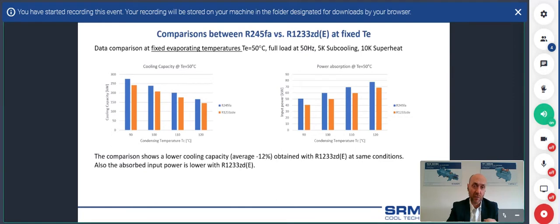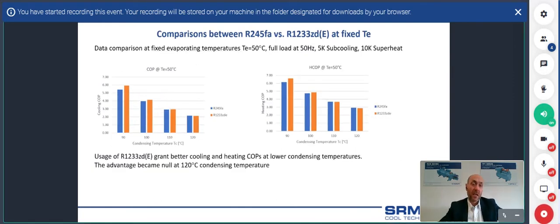So in terms of efficiency of the system, the cooling COP is higher at lower condensing temperature for the 1233. We can see on these two graphs that at 90 degrees C condensing temperature, the cooling COP for the compressor is higher for the 1233. This difference is reducing, and there are practically no differences at 120 degrees C. On the right, we have the heating COP comparison. In the same way, we have higher heating COP at a condensing temperature of 90 degrees C for the 1233, and the heating COP is practically the same at 120 degrees C. So this first look already confirms that the 1233 can be a replacement for the 245 because it has equal or even higher efficiencies than 245FA.